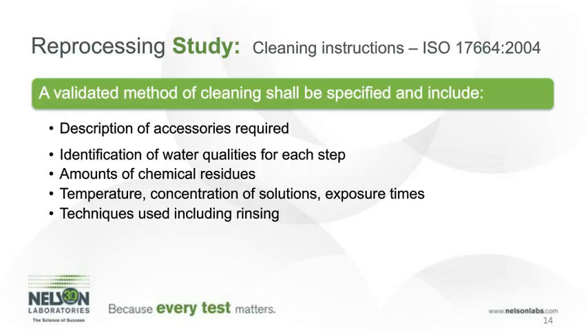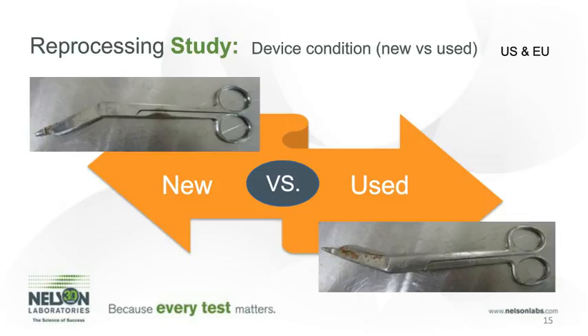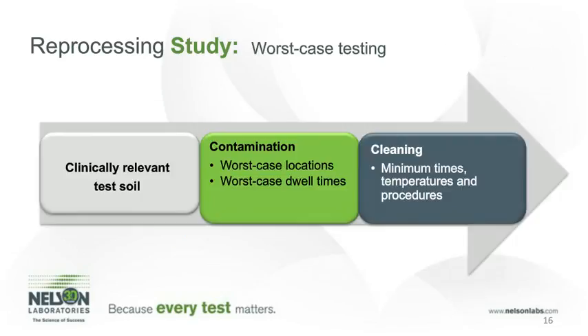One of the first things to consider is the device condition when performing the cleaning and sterilization validations. As we probably know, a new shiny device will be able to be cleaned and sterilized more easily than a device at the end of its use life. FDA has required simulated use cycling, and the number of cycles depends on the type of device. So we want to get the device into more of a use state prior to performing the validations. Another couple of very important aspects of the cleaning validation are clinically relevant test soil and worst-case testing.